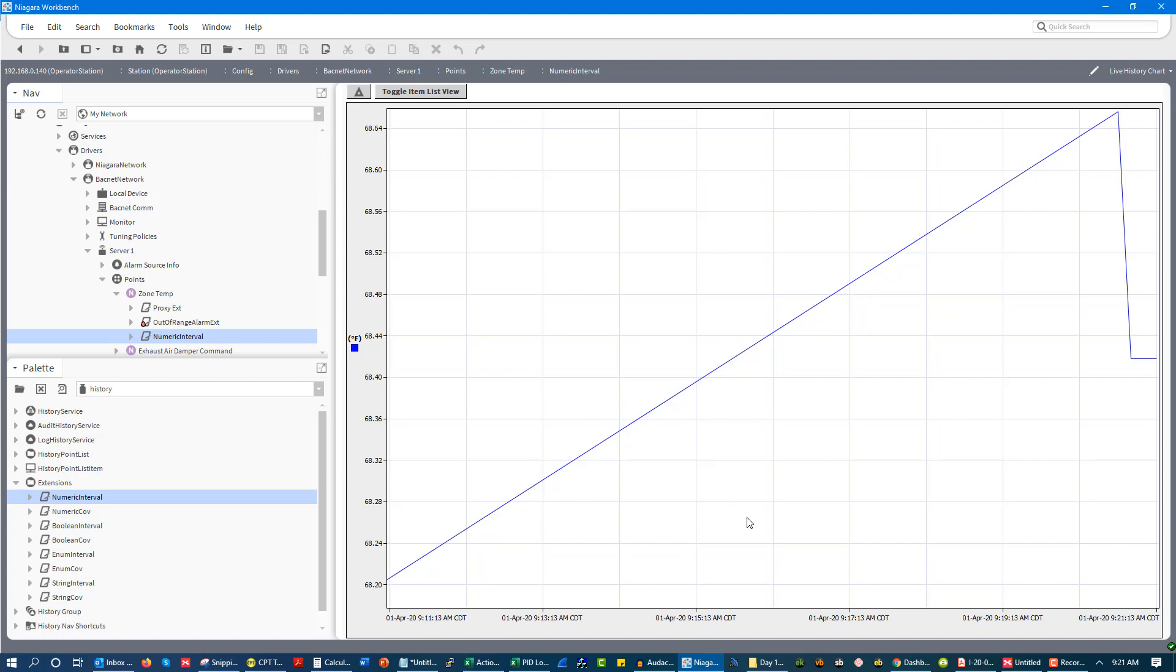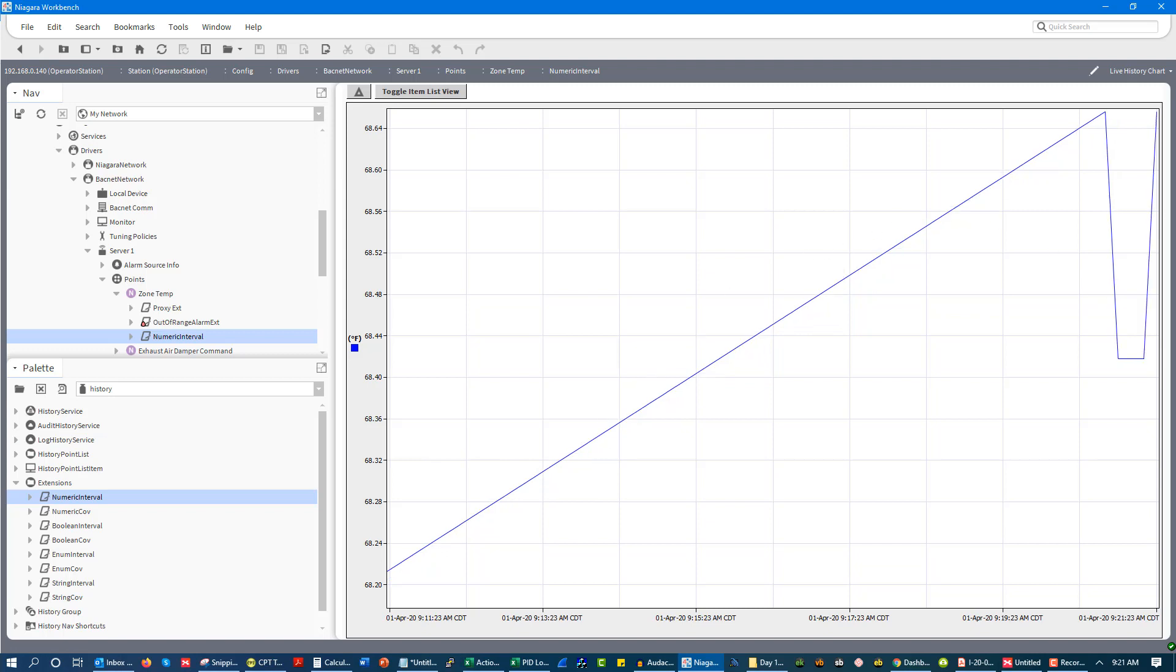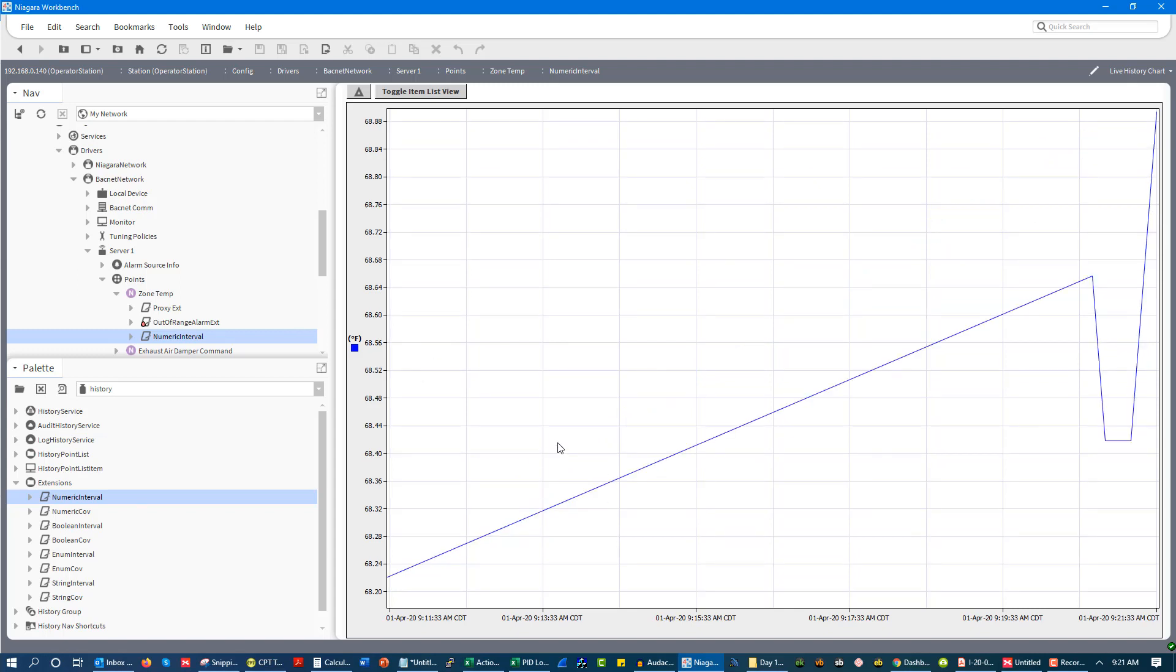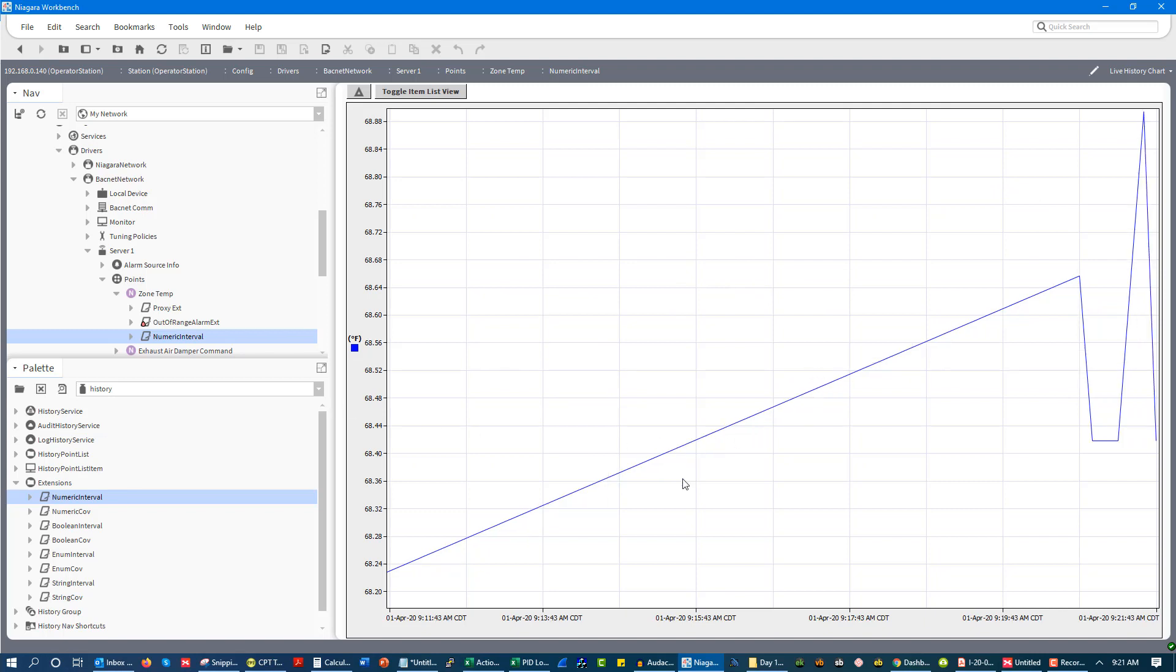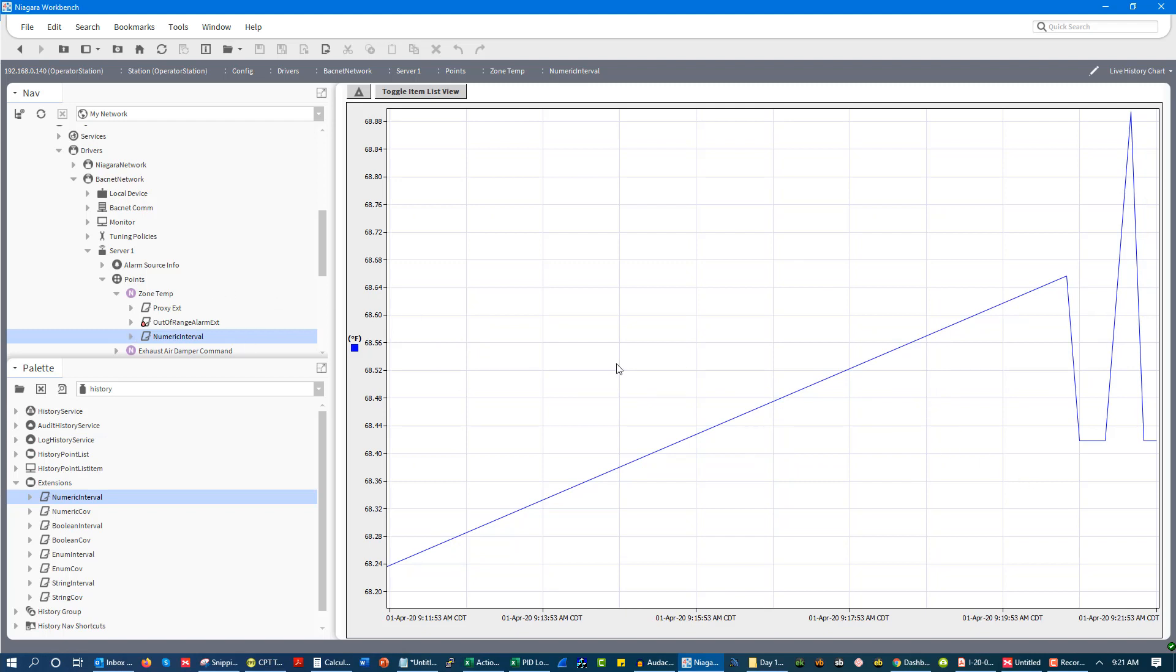So for example, for discharge air pressure, I would probably use a change of value and not a time period trend. Because here's the thing, zone temp, as you can see, the swings in the zone temp are very minor. And with most spaces being four air changes an hour, you're going to see very minor swings in space temp, except for like when a bunch of people enter the space or when morning warm up or cool down starts off. Other than that, the space temp is not going to change a whole lot, but pressure is going to change quite rapidly. So you would rather than using an interval, you would want to use something like change of value.